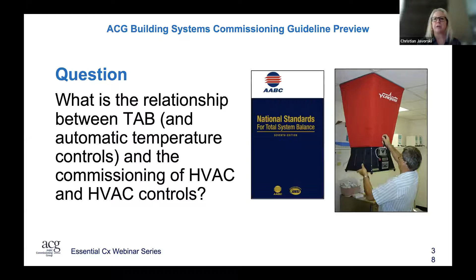Do you have to have TAB and controls on site at the same time? I highly recommend it, although sometimes it doesn't happen. It's recommended so everything can be finalized as needed, with manipulation of the system happening during construction with the TAB guys on site, so we don't miss any set points and make sure everything is working properly when we leave.